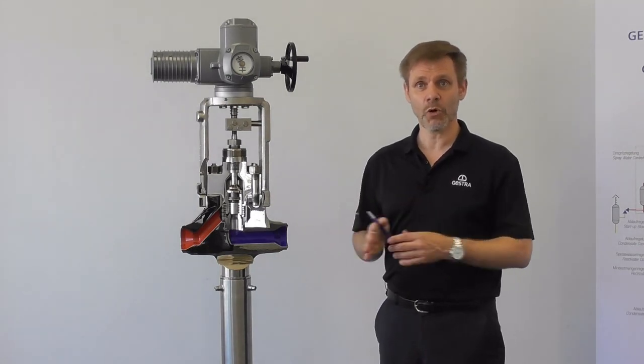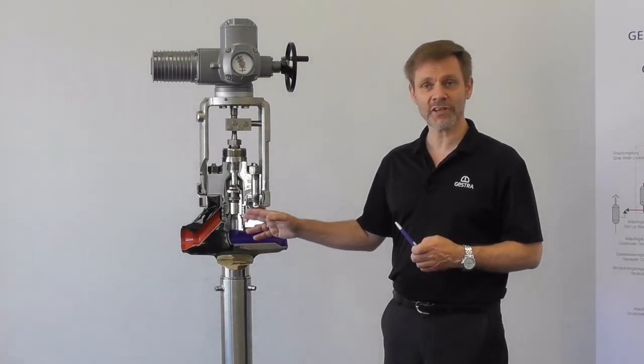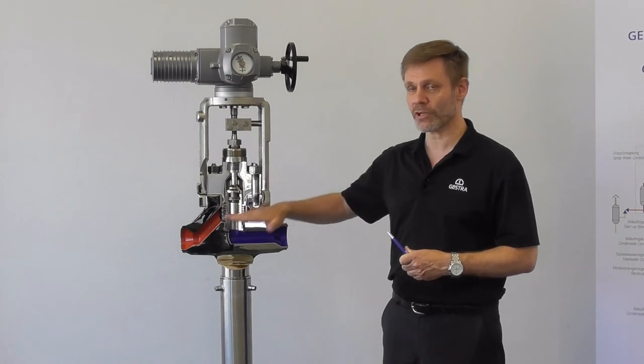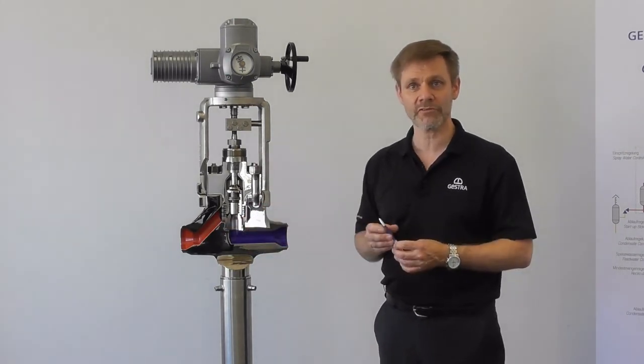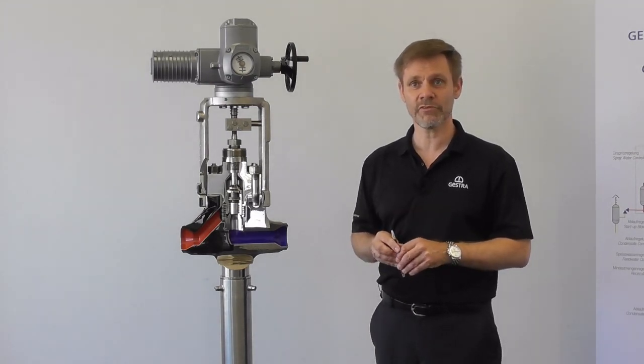At the end of the day, all parts are changeable including the seat. That means you have easy maintenance. The valve body stays in the line and you can pull out all internal parts out of the valve and replace them with new ones if necessary.